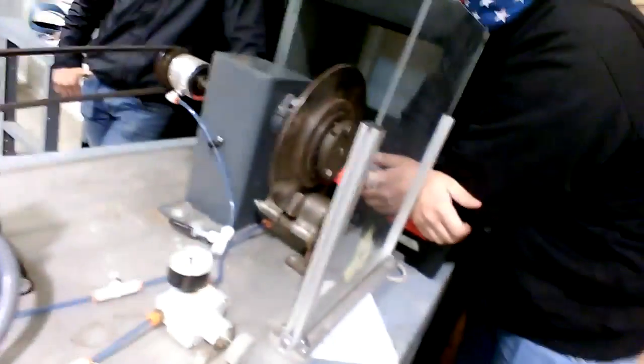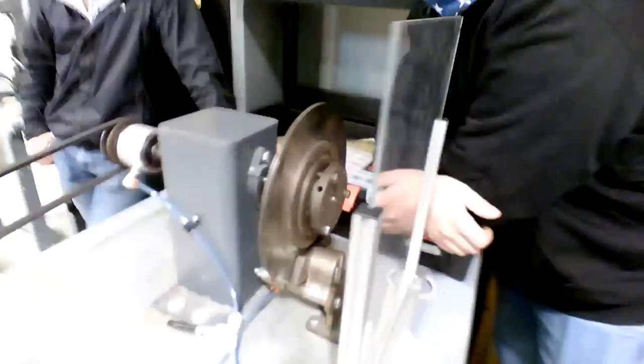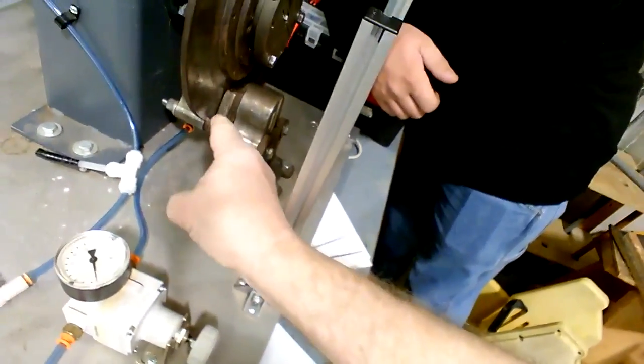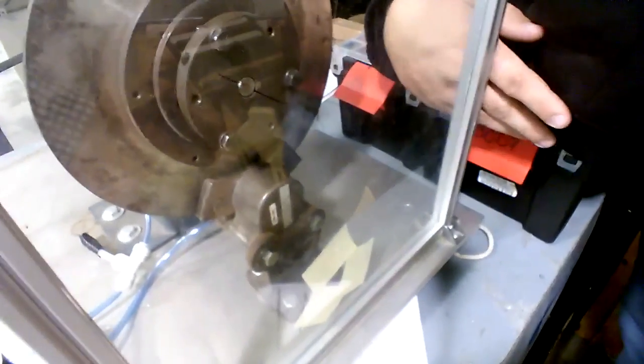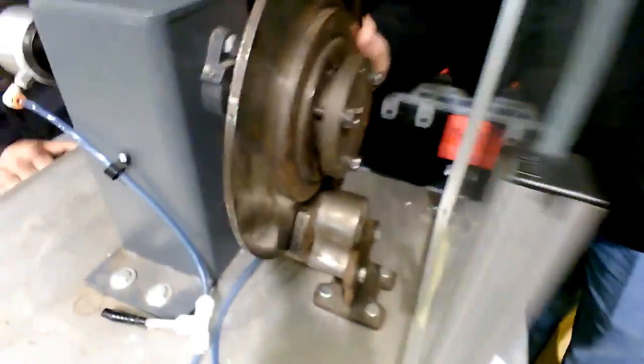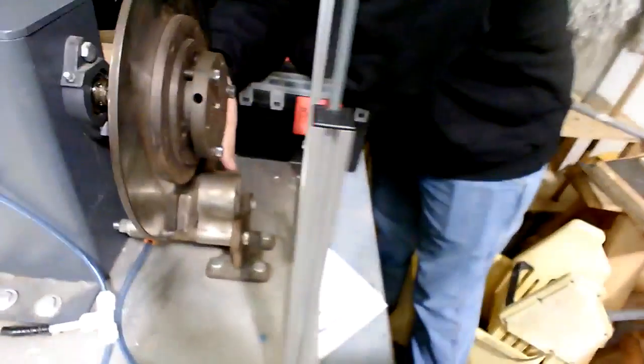You guys have any comments you want to say to Patrick and Brandon? What are your thoughts when you made the adjustments? Tell them how you got the gap fine tuned in here. How did you get that gap fine tuned without having to break the taper lock loose, without having to go and change the QD bushing? That QD bushing is a big headache to try to make an adjustment because it's very time consuming. So that last fine tune, that gap in there on that backing pad, tell them how you did that.